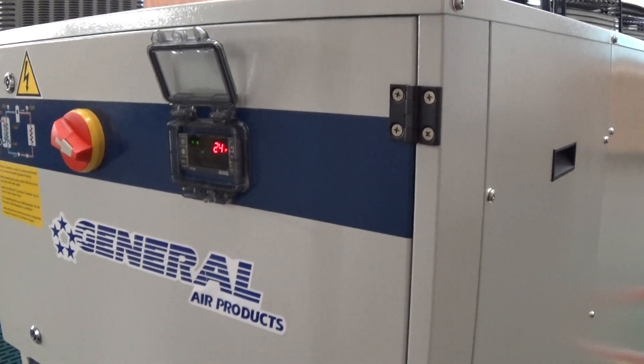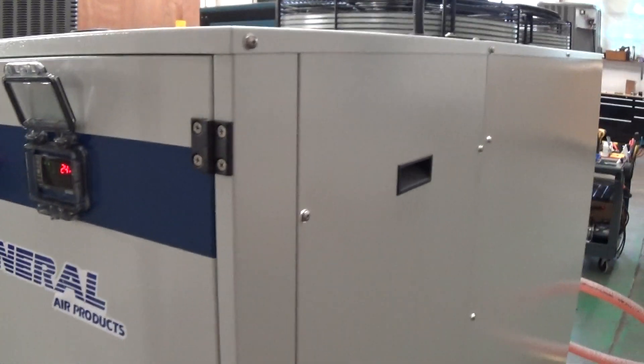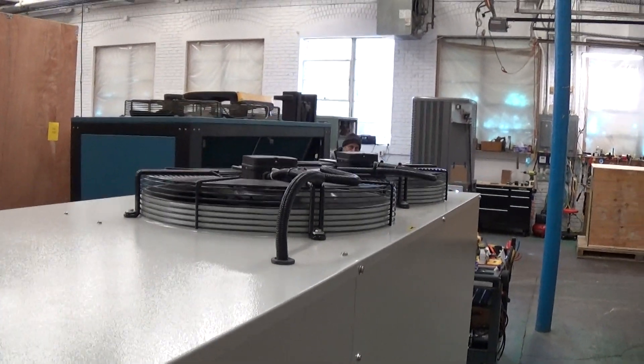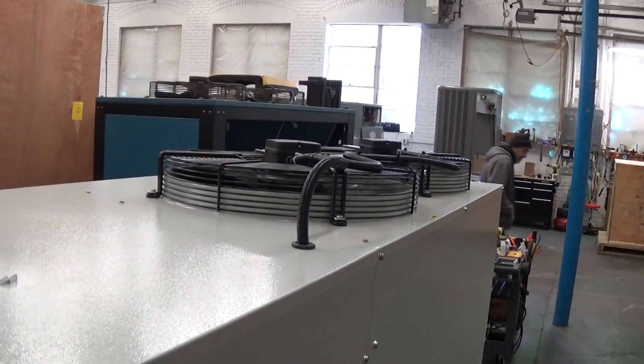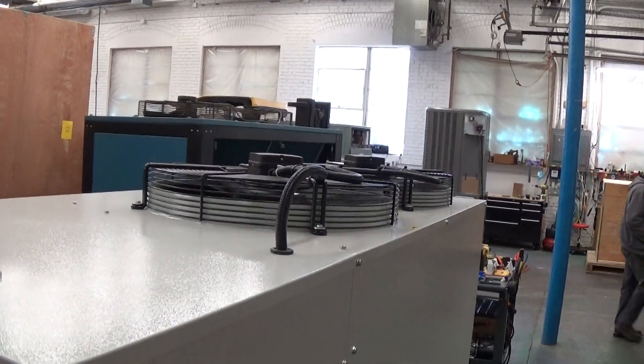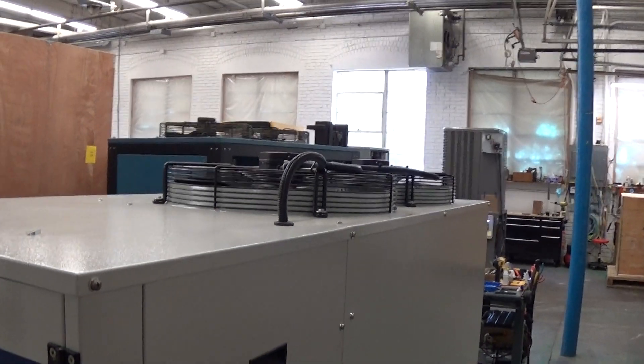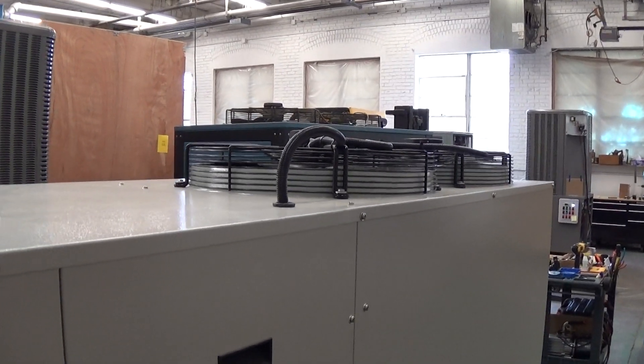With such a small load and the temperature in our shop here, the fans are going to cycle on and off fairly quickly. The low ambient feature capability is achieved by these fans going on and off based on refrigerant pressure.